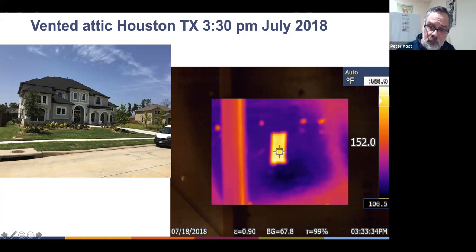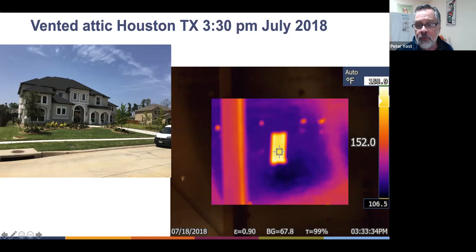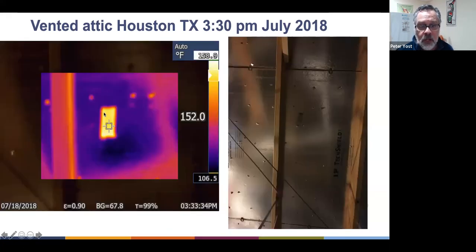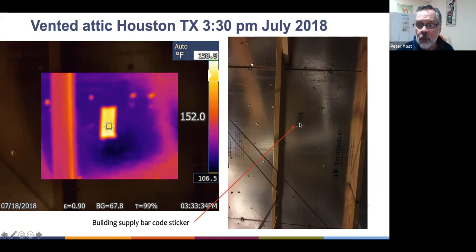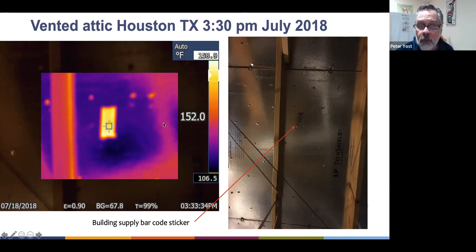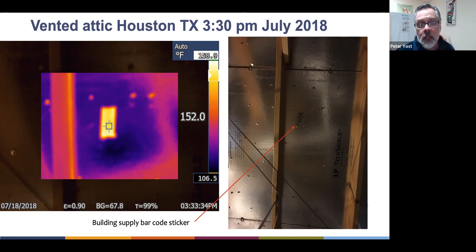This illustrates the difference between relative and absolute temperature differences. The relative temperature differences in this infrared image are accurate, but because the background temperature was not set to 100 degrees, the absolute temperatures are probably a bit off. And the bottom of the mystery — this image is taken right here. So why is this spot so warm? That's the building sticker — the barcode sticker for the sheathing. Look at the impact: we went from radiant foil with an emissivity of about 0.05 to a sticker with an emissivity of about 0.9, and the surface temperature difference is about 40 to 50 degrees.